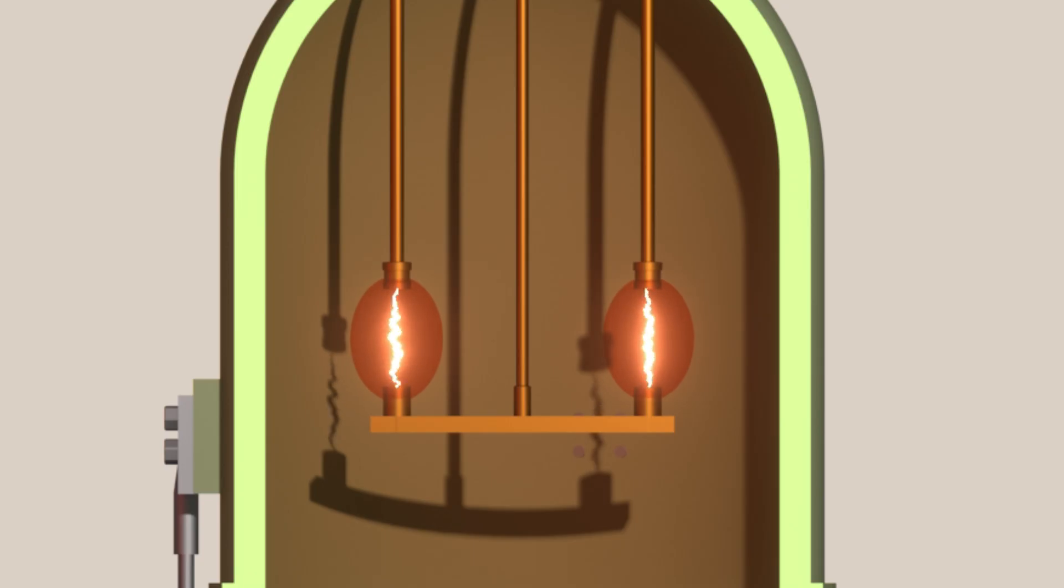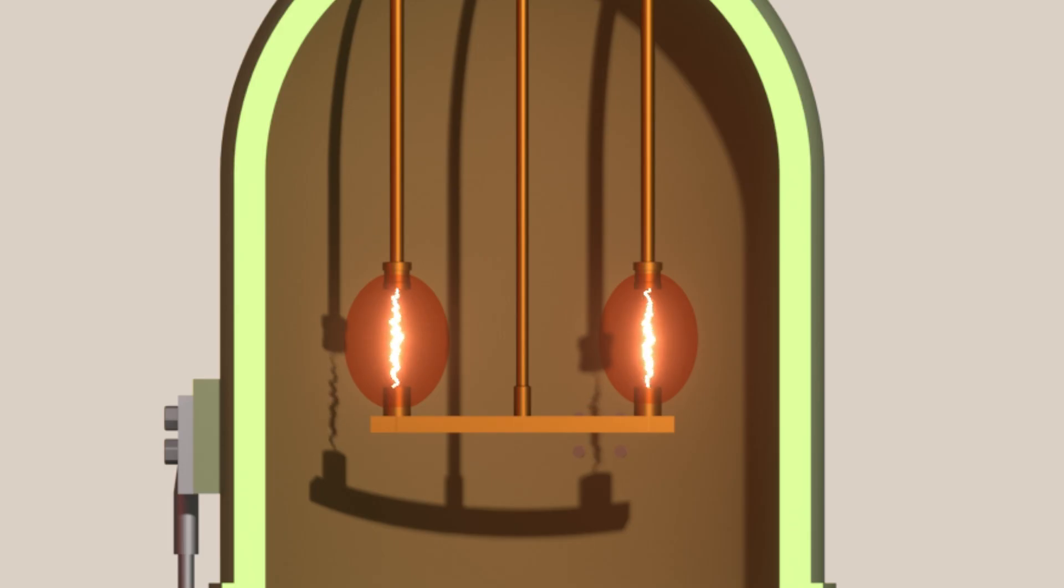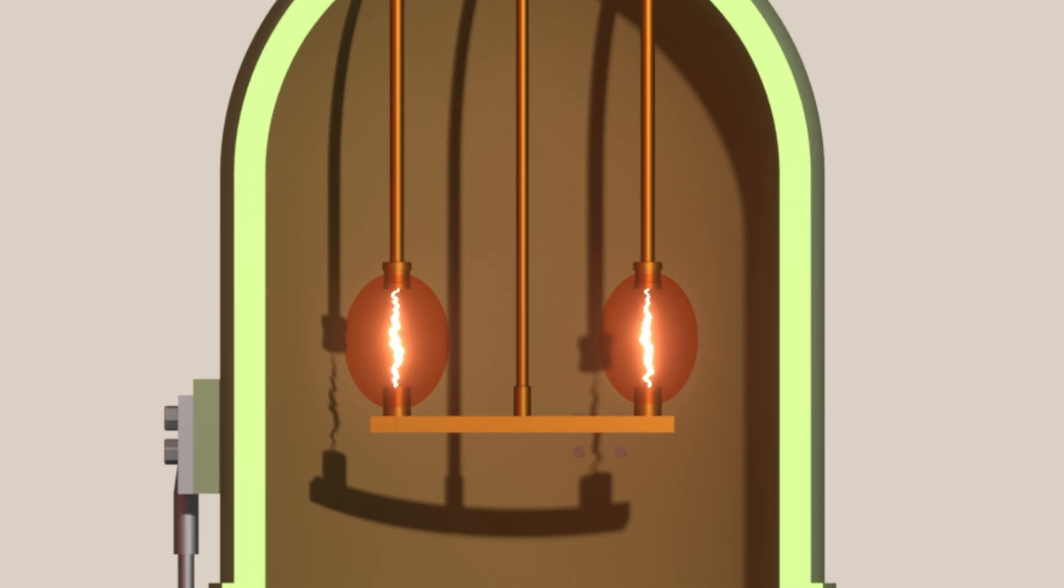Due to the high surrounding oil pressure, the bubble size cannot increase as quickly as hydrogen gas is produced. This increases hydrogen gas pressure. Hydrogen has excellent cooling and deionizing properties, which help in arc extinction.